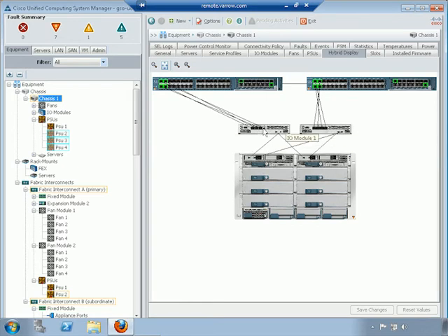Well, then this FEX has 4 connections that go to interconnect A, and this one has 4 that go to B. So you can literally see that fabric port 24 here goes up to Ethernet port, I believe that is port 14. But you can see that it actually draws the lines, and this is physically correct, meaning whatever lines these things connect are actually what's plugged in to the back of the FEXs to the interconnects. It's a quick and dirty way to see how many ports are connected and how your servers are lining up.